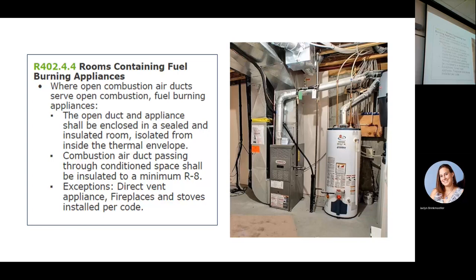Because the big reason that was put in the code is because they reversed all the B vents. You eliminate the B vents, we have eliminated the risk. Now, it's still not going to work very well if you put in a 1200 CFM fan and it can't get any air. You're still going to smoke up your kitchen because it can't get 1200 CFM replaced, but we've eliminated the hazard of reversing the B vent.